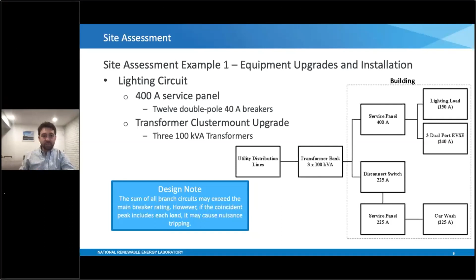Then after that, you want to look at, if we're upgrading the service panel, how do we get this electricity from the new service panel to the location needed for each of these EVSE? And as I mentioned, we're installing wall mount units, so we thankfully won't be requiring any trenching, but it is important to note that trenching is a rather expensive cost, and it can be one of the most expensive costs of an EVSE installation. Some estimates can be around $100 per foot or more, potentially upwards of $150 per foot, just to trench out to the EVSE.